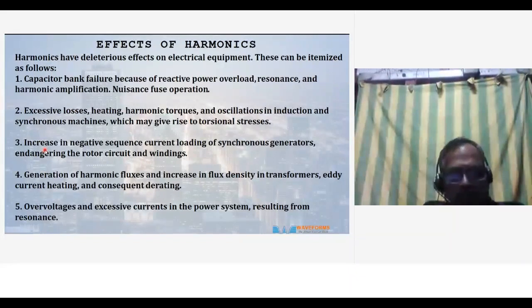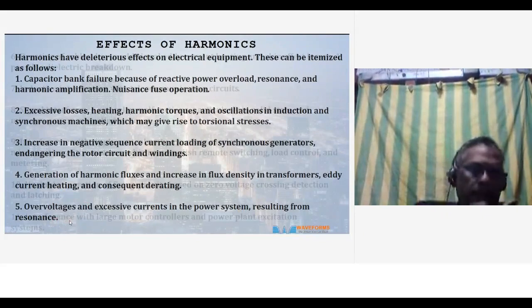Generation of harmonic fluxes and increase in flux density in transformers. So the transformers get saturated because of harmonics, with eddy current heating and consequently derating. This results in many using K-rated transformers to absorb this heat. They don't mitigate harmonics, but they withstand the thermal stress. That's called K-rated transformers. Overvoltages and excessive currents in the power system result from resonance. I'll come to the subject of resonance later. So these are all the ill effects of harmonics.